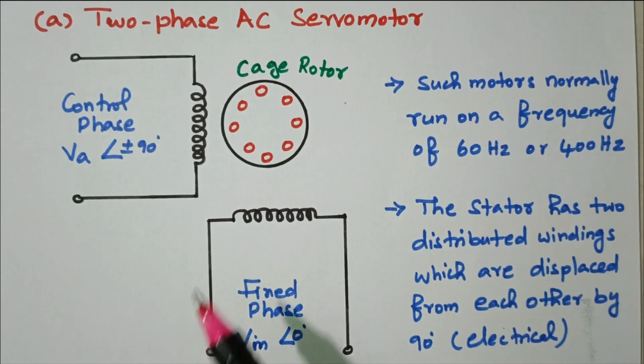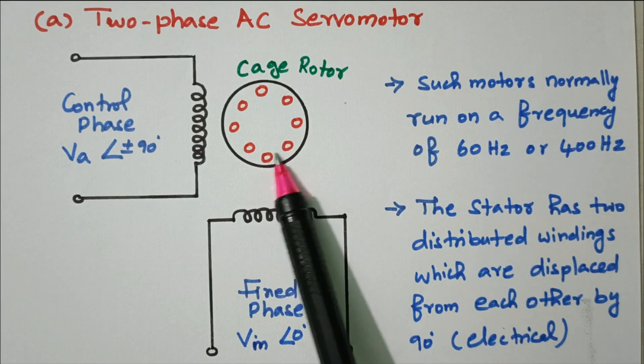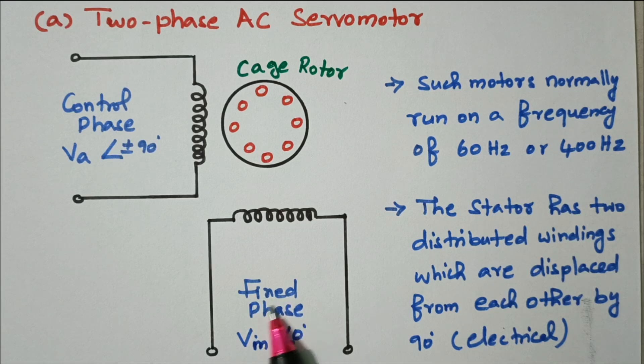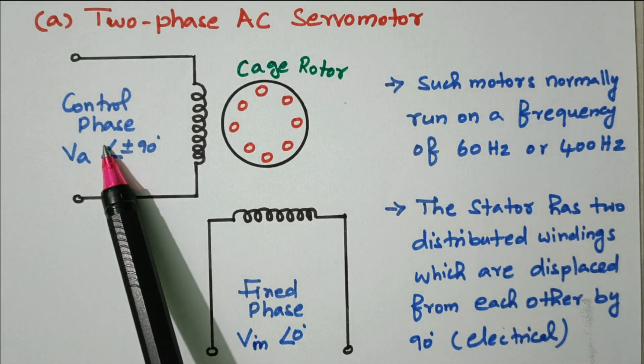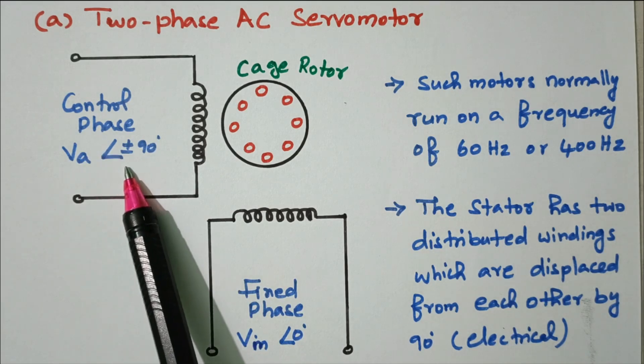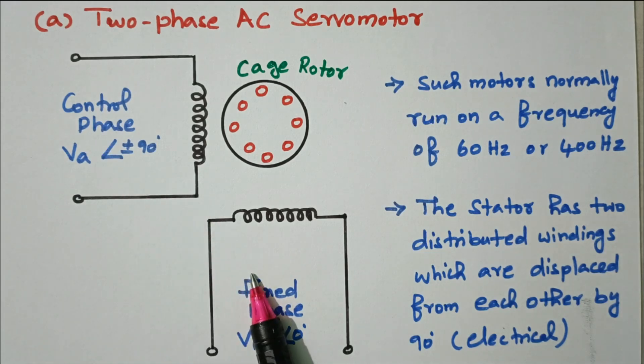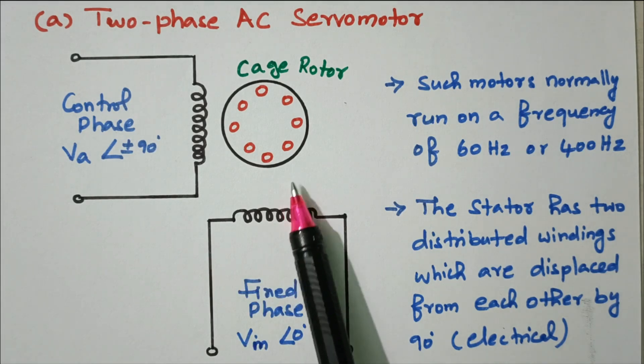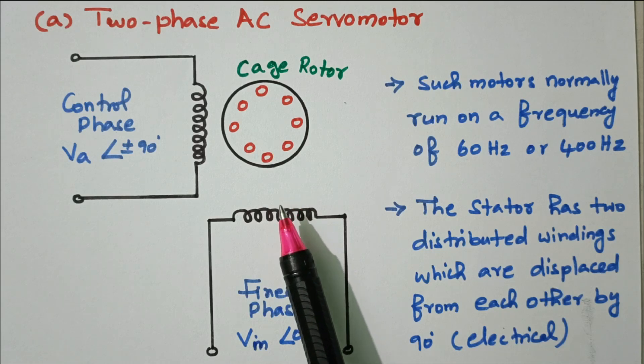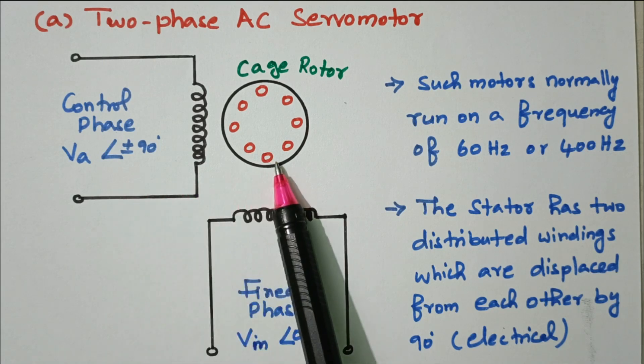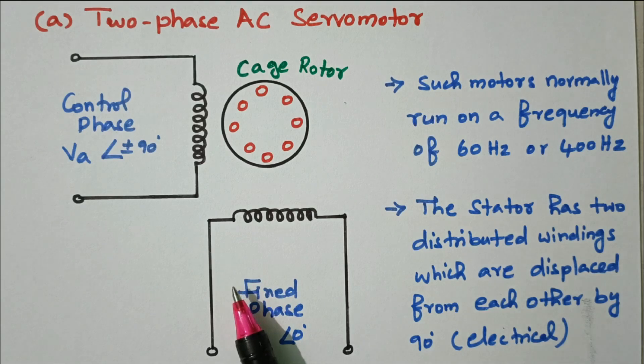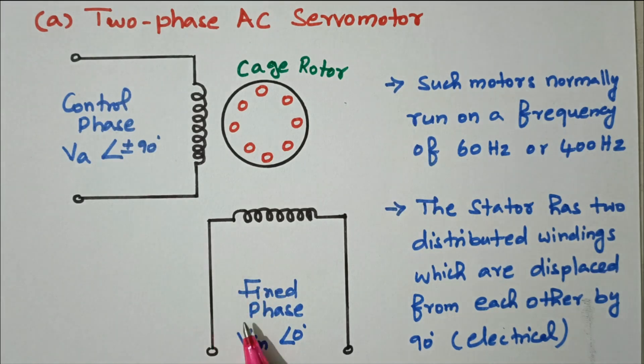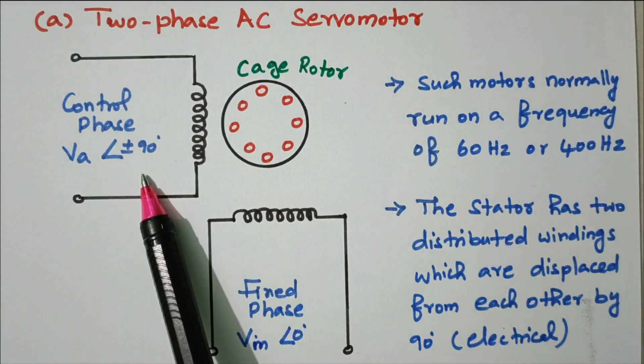This is a two-phase AC servo motor. The squirrel cage rotor is available; the bars are fixed and the coils are fixed. There are two phases: one is the fixed phase where Vm is the applied voltage at angle zero, and another is the control phase where the applied voltage Va is at plus or minus 90 degrees. The phase difference between fixed phase and control phase is 90 degrees. Any small change in current or voltage in the control phase will be reflected in the speed or position of the rotor — this is the main advantage of this servo motor.